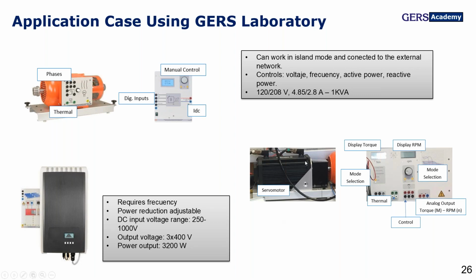Now we have our servo machine, and with this servo machine we are also able to control the RPMs when the synchronous generator is disconnected from the network, or the torque when our synchronous generator is connected to the network. In island mode, we will have control of the frequency where our frequency reference will be the servo machine, and in connected mode, our servo machine operates in torque mode.